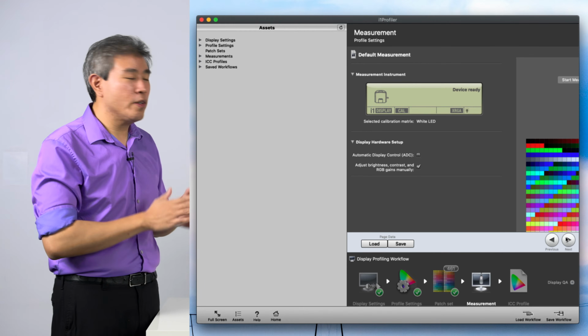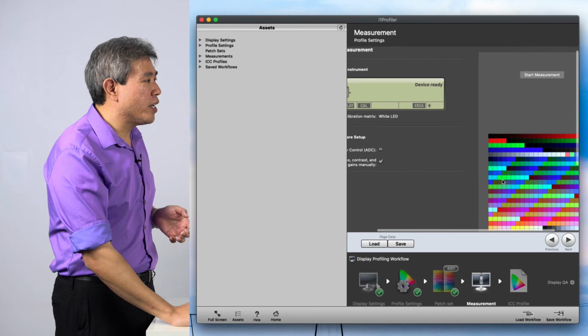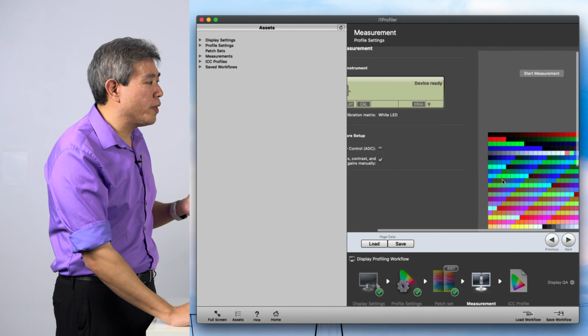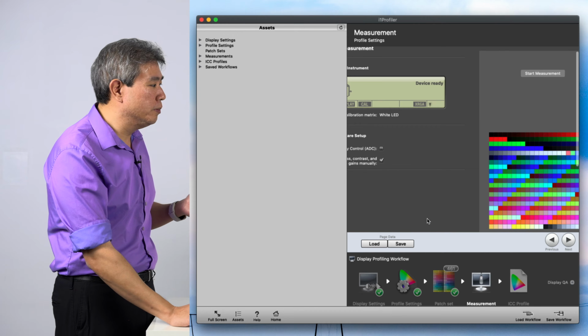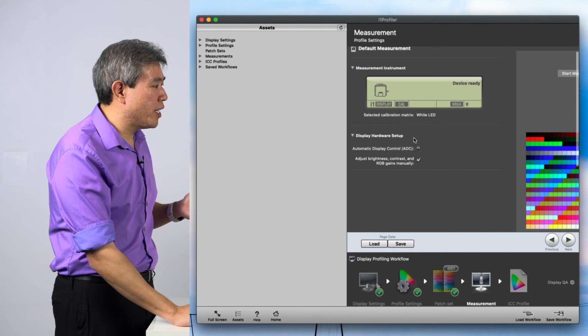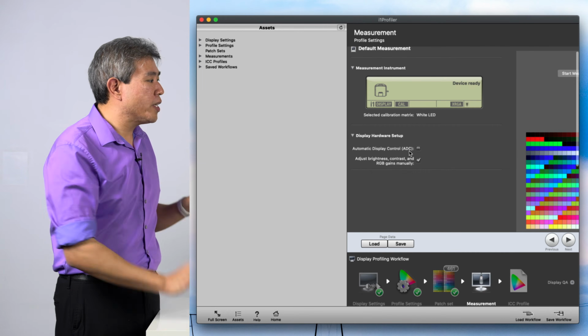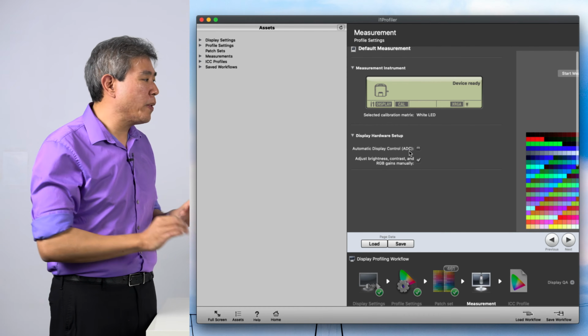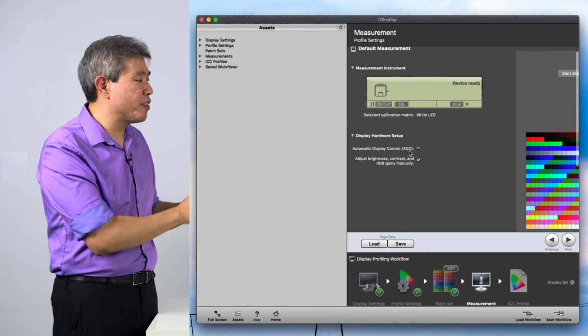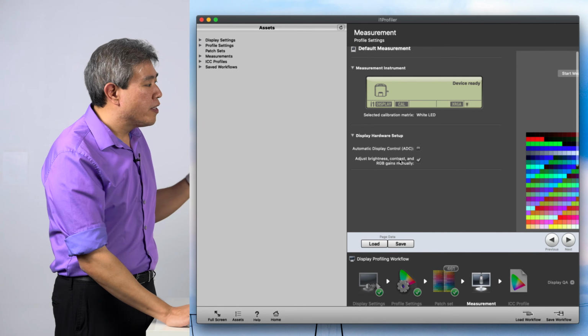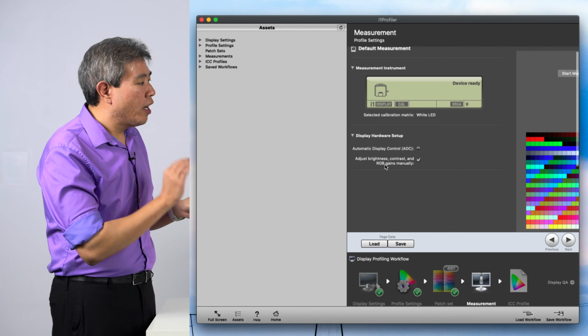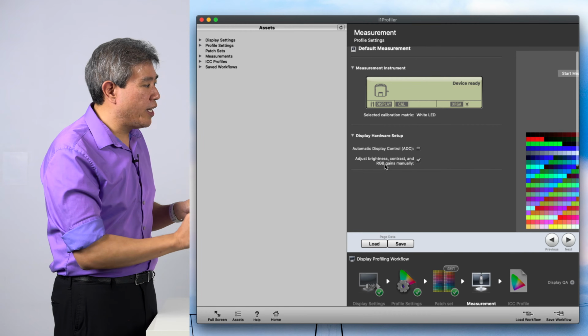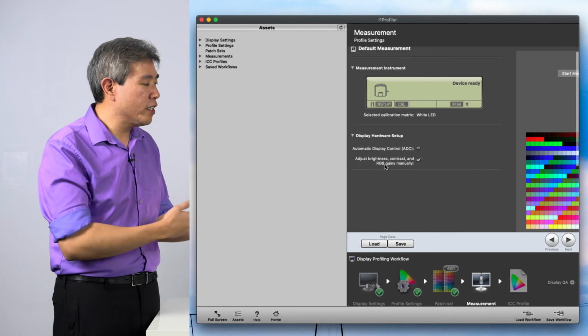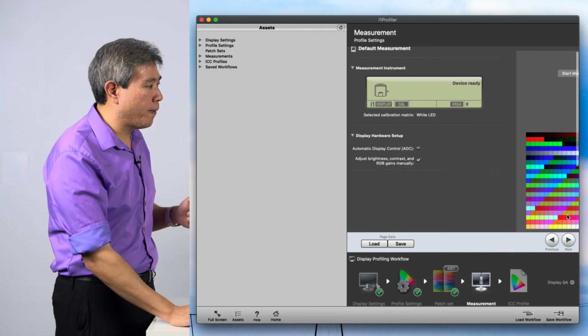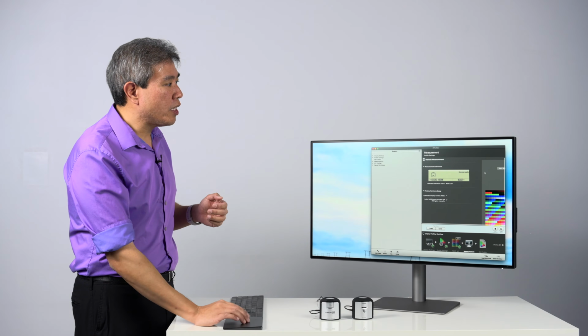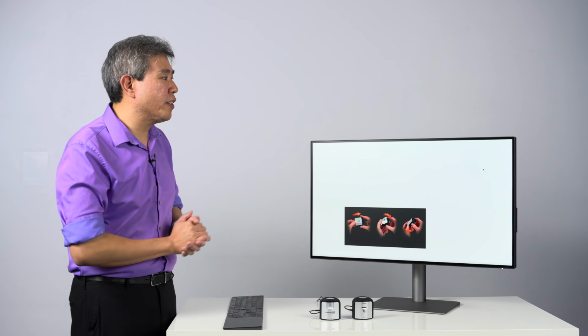This is going to take us to the measurement screen. In this screen, we can click on start measurement right away, but before we do that, what I want to do here is go over a few more settings. I'm going to make sure that automatic display control is unchecked because I want to go in and manually adjust my display brightness. Secondly, I have checked adjust brightness, contrast, and RGB gain manually. So make sure that is checked so that you can go in and change the brightness appropriately. From here, if you scroll over, you can click on start measurement.